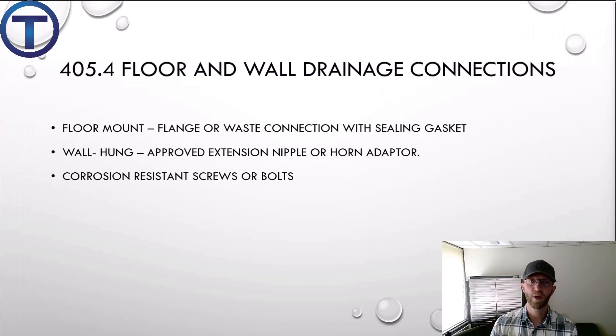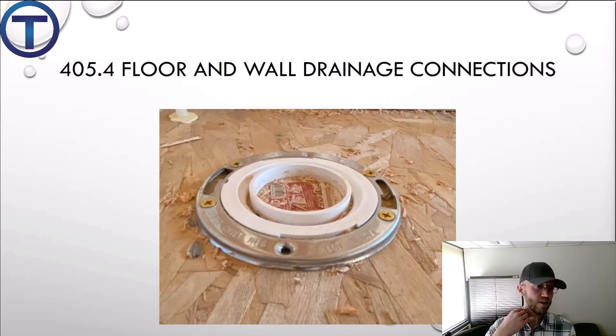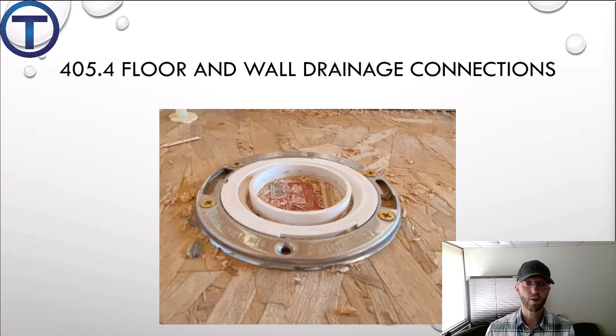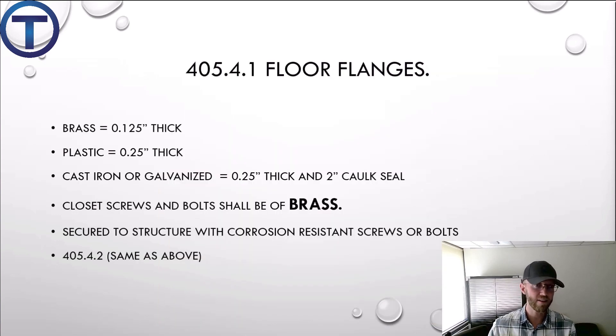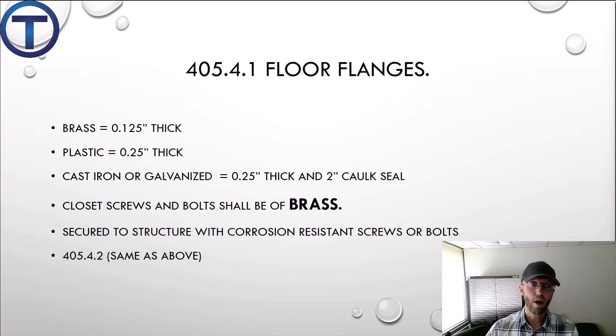405.4 covers floor and wall drainage connections. There are two basic ways to hook up a toilet: set it on a flange on the floor, or hang it on a carrier on the wall. In either case, corrosion-resistant screws and bolts must be used. Here's an example of a floor flange fastened to the subfloor using brass screws — brass is a corrosion-resistant material, specified in 405.4.1. Flange thickness details: brass at 0.125 inches, plastic at 0.25 inches, cast iron or galvanized at 0.25 inches. The screws or bolts must be brass and secured to the structure.